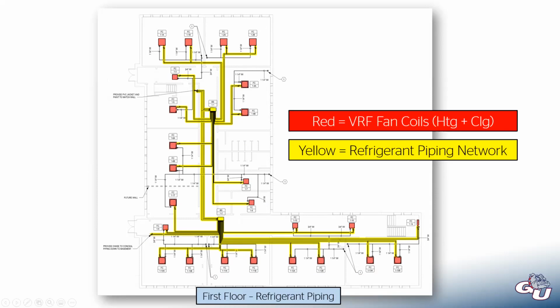VRF is a very efficient system because of that reason: spaces in different operating modes can share that energy, which means ultimately the heat pump outside doesn't have to work as hard to get that heat, because it's instead using heat that's already in the building. We're just moving it around to wherever it's needed.